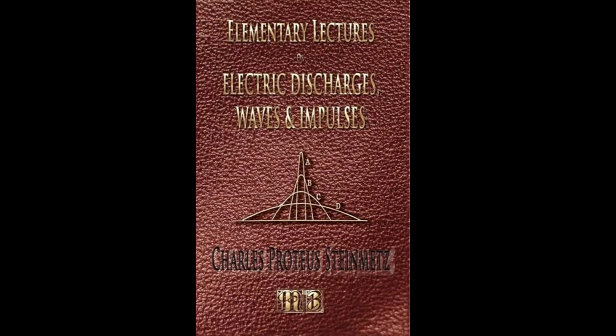That is, if I0 equals field exciting current, N equals number of field turns per pole, R equals resistance, and L equals inductance of the field exciting circuit, it is hence I0 squared R equals 500, R equals 500 over I0 squared. That is, the stored magnetic energy could maintain full field excitation for nearly 4 seconds. It is interesting to note that the duration of the field discharge does not depend on the voltage, current, or size of the machine, but merely on, first, the magnetic flux and MMF which determines the stored magnetic energy, and, second, on the excitation power, which determines the rate of energy dissipation.